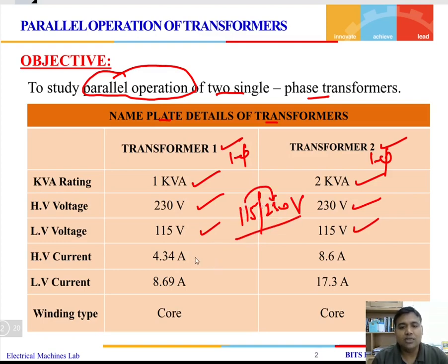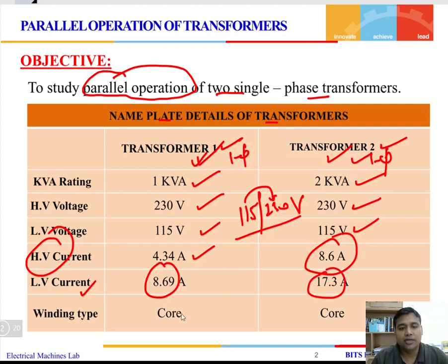The high voltage current is 4.34 ampere for transformer 1, and for transformer 2 it is 8.6 ampere. For the low voltage current, we have 8.69 ampere on the transformer 1 side and 17.3 ampere on the transformer 2 side. Both windings of the transformers are of core type.